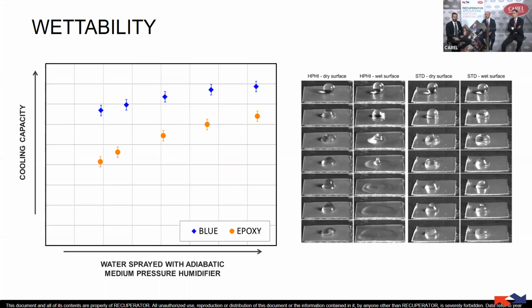So thank you. These are very important differences coming from different surface treatments, but at the same time it's important to select the right configuration, the combination of humidifier and heat exchanger for the indirect evaporative cooling. So, can you add some more suggestions on choosing the right configuration of the system? We have focused up till now on the heat exchanger, but of course the system is a composition of two things.